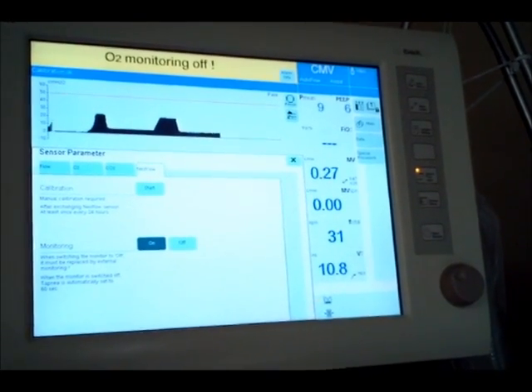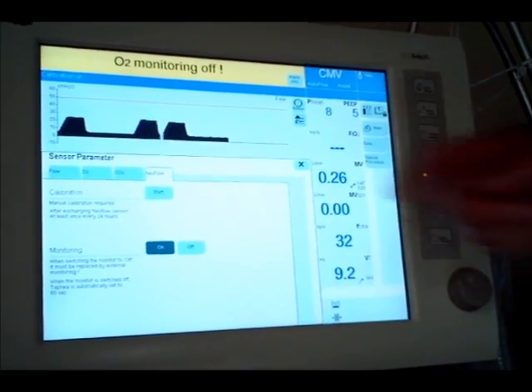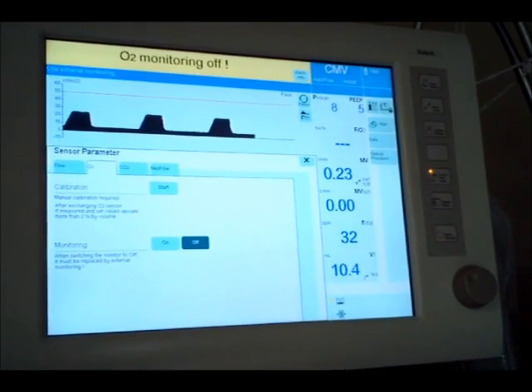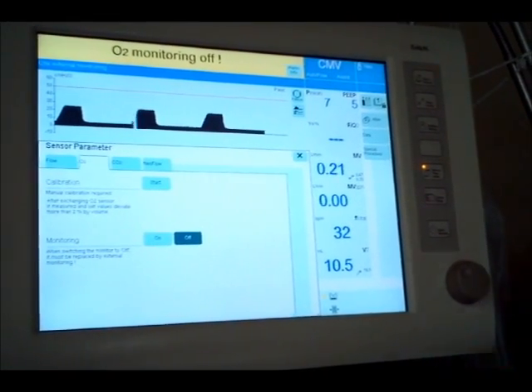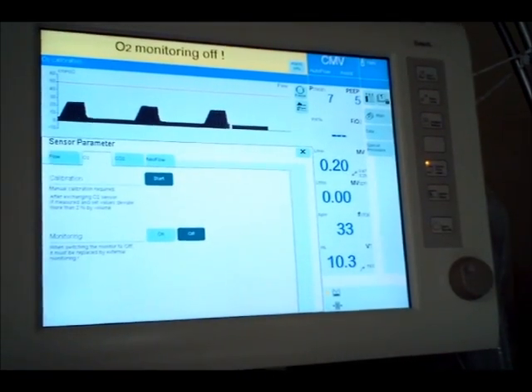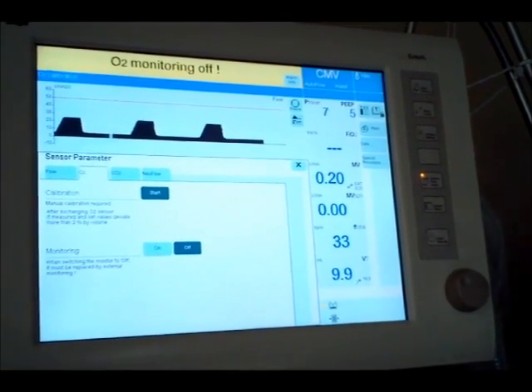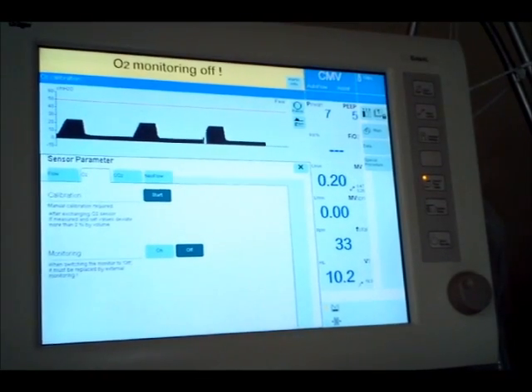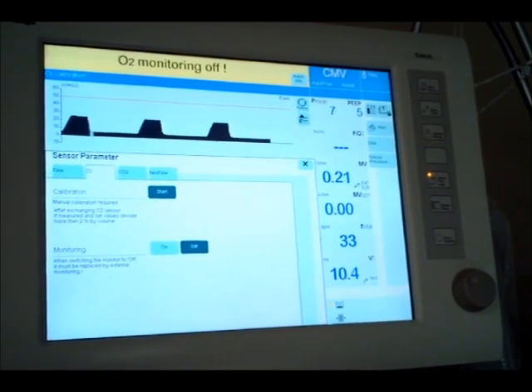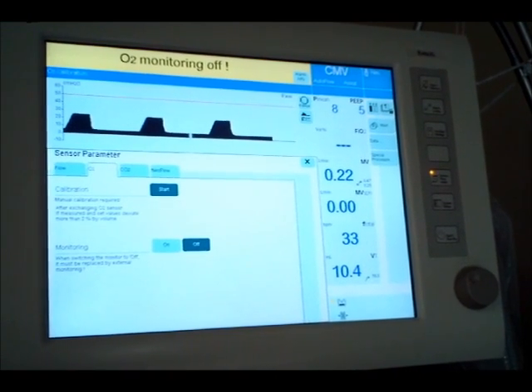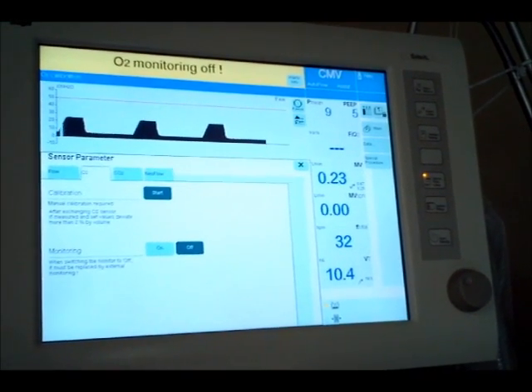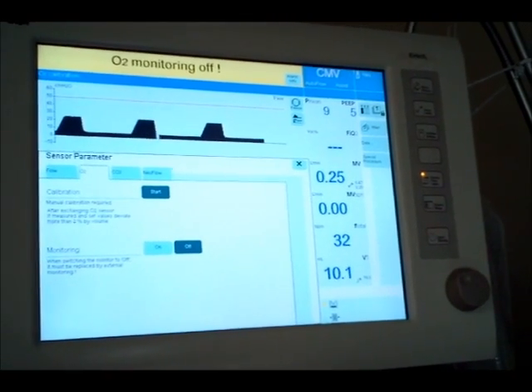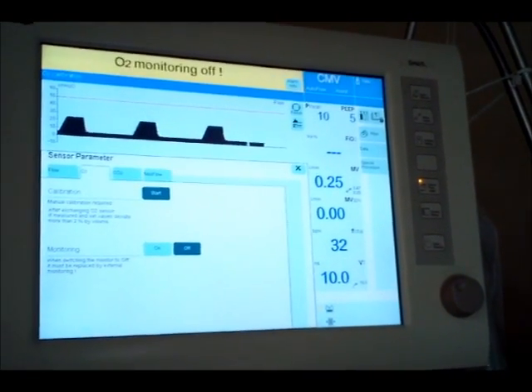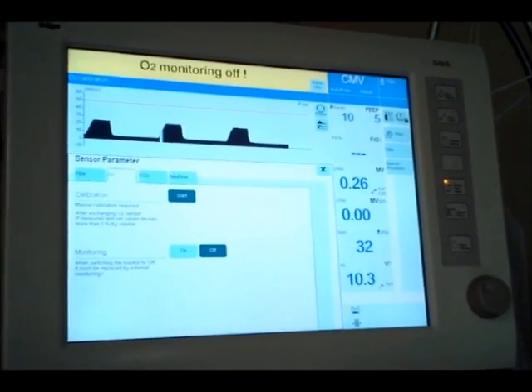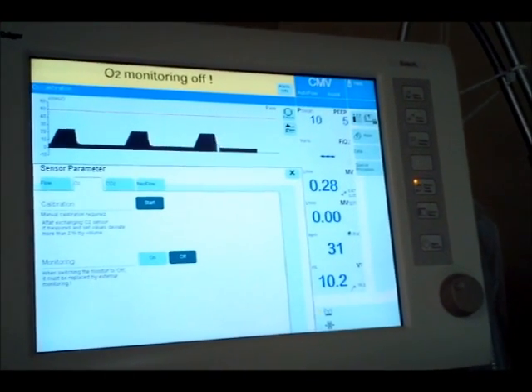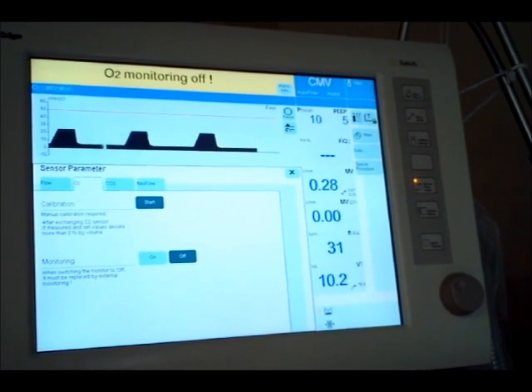And then calibrate the oxygen sensor. It's the same panel calibration. We'll go ahead and do that. We'll see what happens. It's going to say O2 calibration, doesn't affect ventilation or anything. So that's something you can do while it's on location. And then you can see troubleshoot and correct any problems. That's if something comes up or something weird happens and you don't figure it out, or you did something slightly wrong but not majorly wrong.